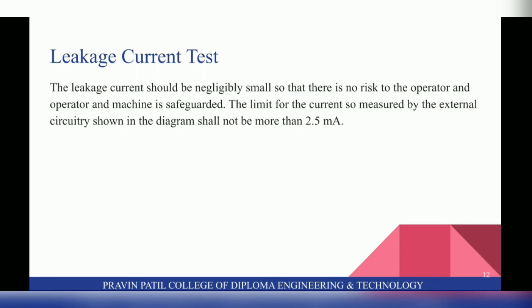Next is leakage current test. The leakage current should be negligibly small so that there is no risk to the operator and machine is safeguarded. The limit for the current so measured by the external circuitry shown in the diagram shall not be more than 2.5 milliampere.